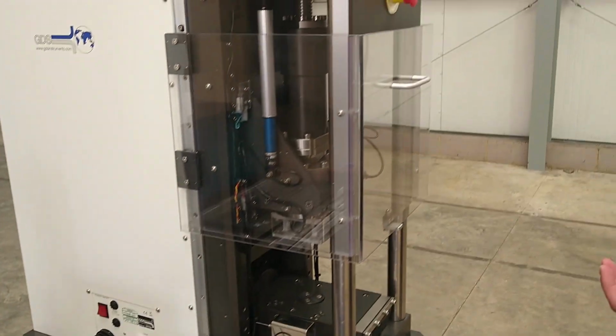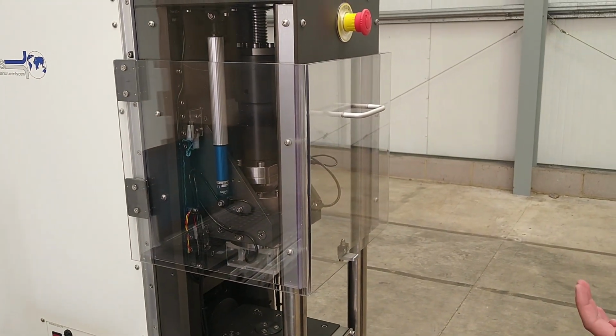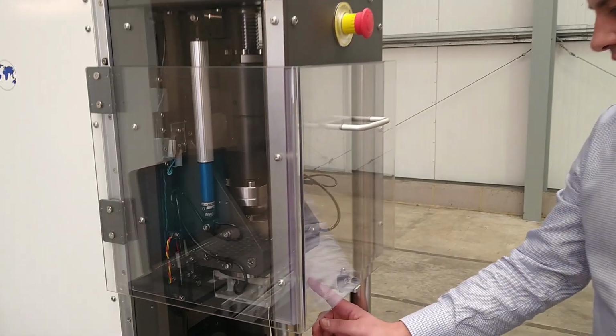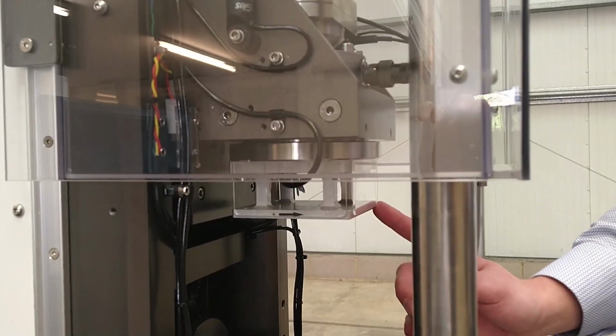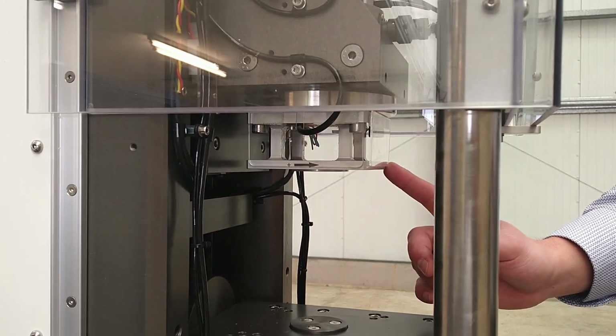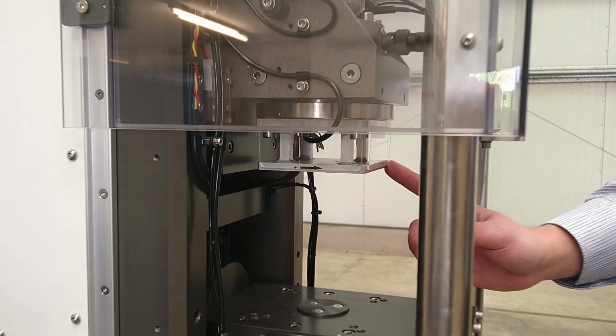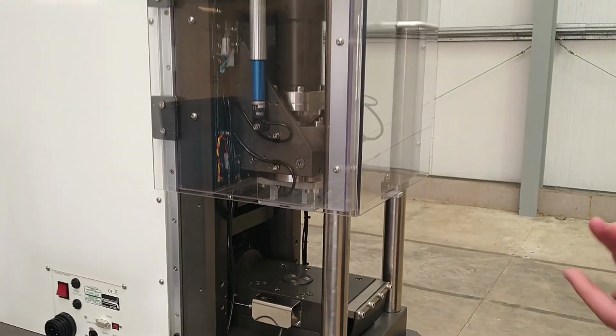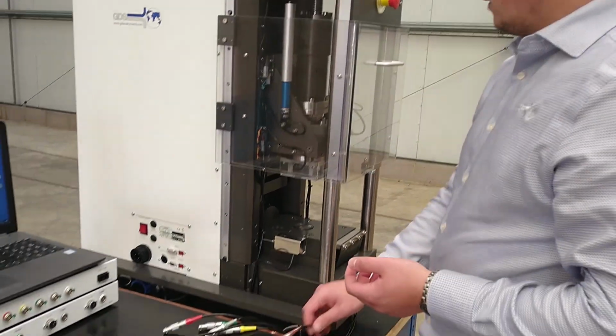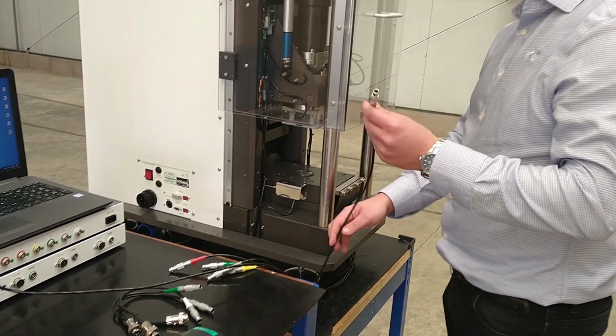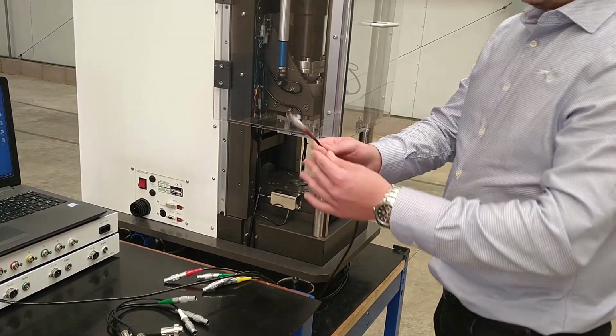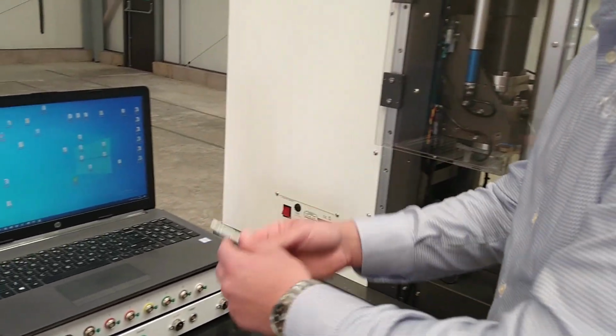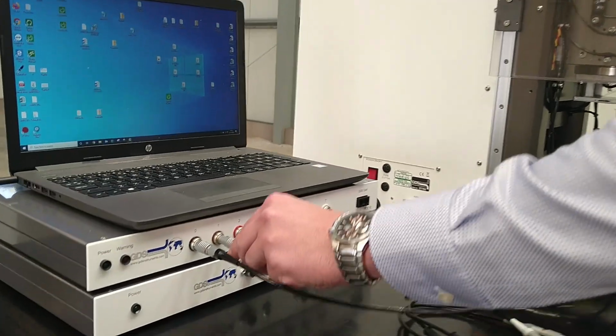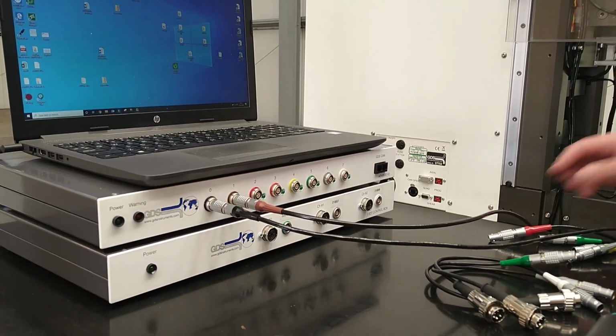Then the second transducer will be the main shear load cell, which sits right over here. This is the load cell that directly measures the shear force on the sample without picking up any of the friction inside the machine. It is color-coded with brown Lemo sleeve and will connect to channel number 1.